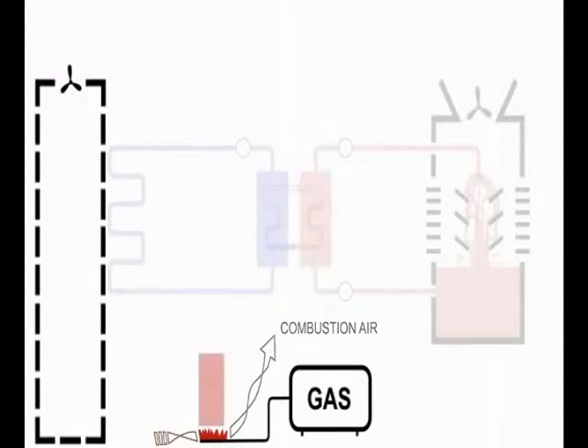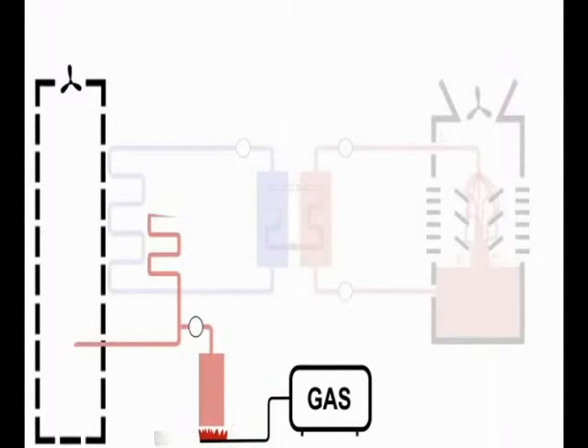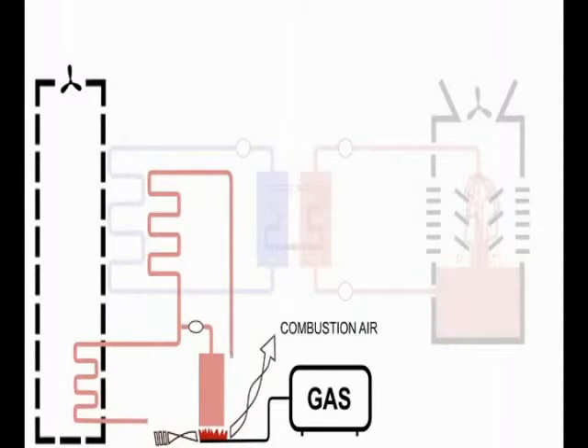The burning fuel heats water in a boiler, and that water is distributed, either as hot water or as steam, via another loop to coils in the air handling unit. In the cooling season, the chilled water loop is activated, but during the heating months, the hot water loop is activated.